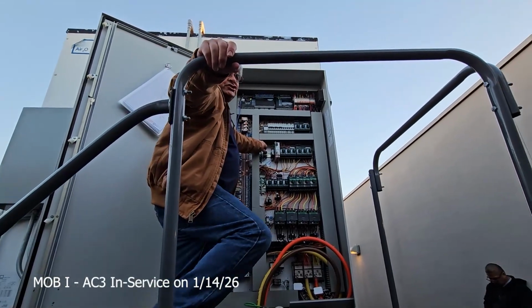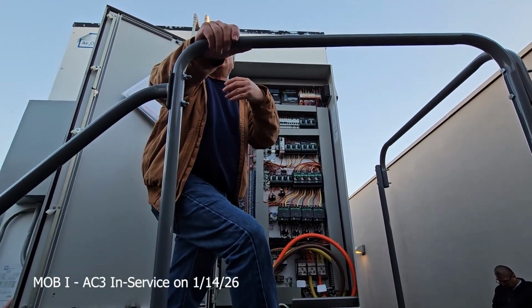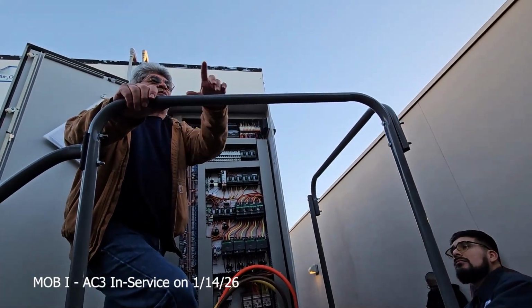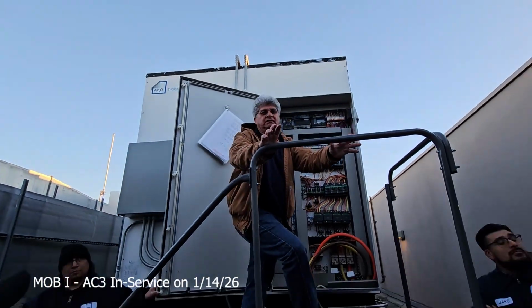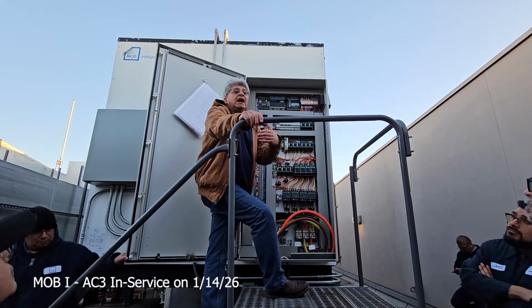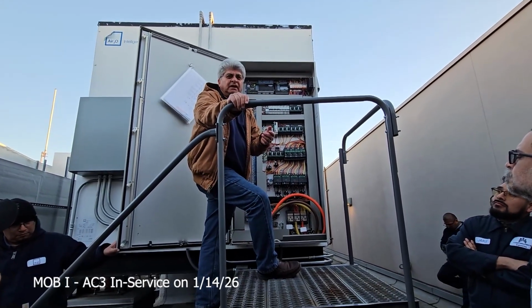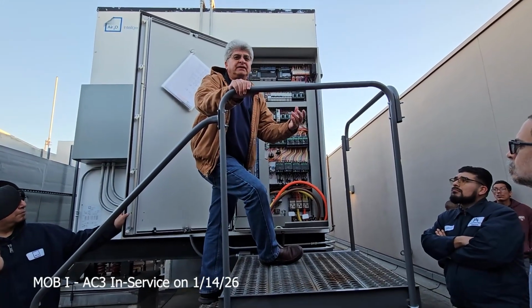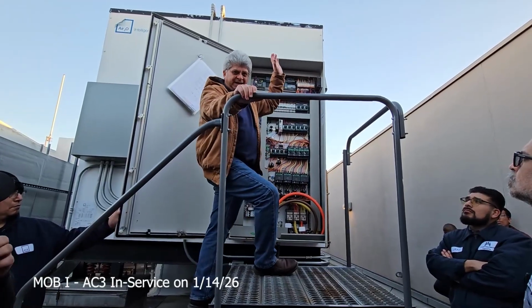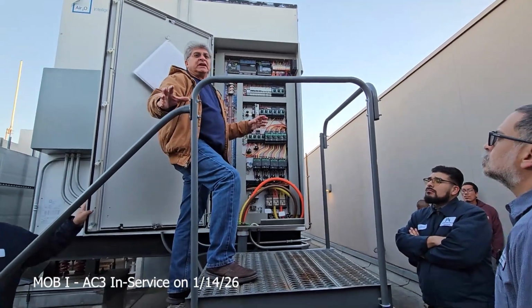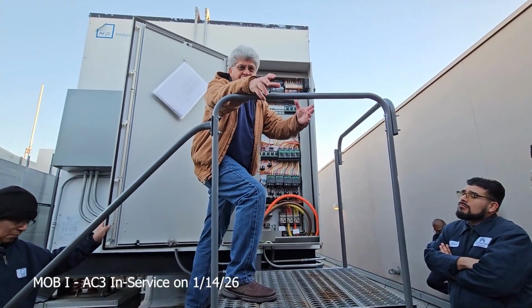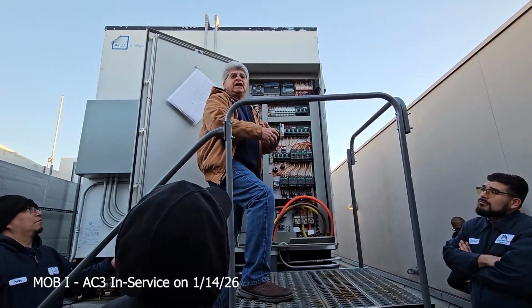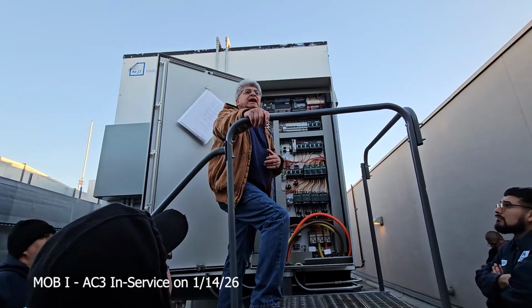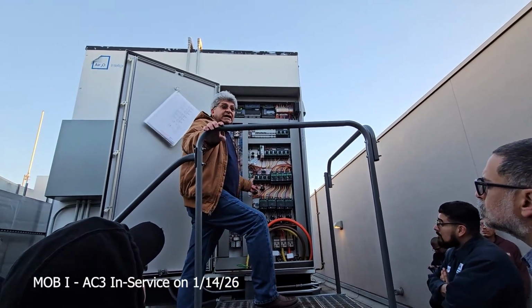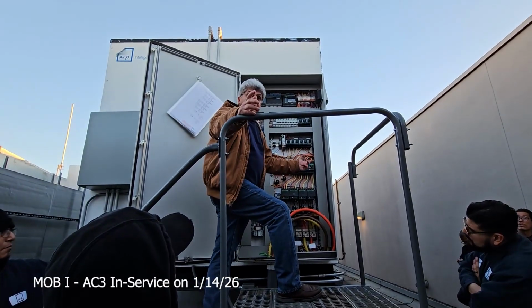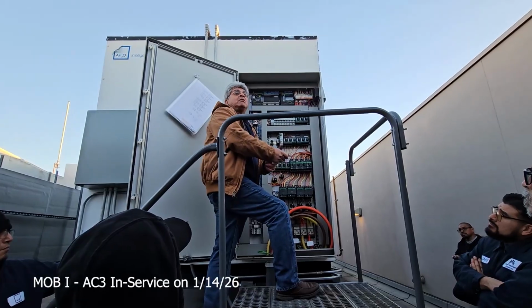To replace that, do we have to shut off the whole unit to replace that fan? My service guys would not. Your boss dictates your safety, how he wants you to work. Right? When I change an outlet in my house, I don't shut off a breaker. I've changed 460 volt breakers live because I had to for the data center. But that's me. That's a couple of my guys that have experience. But I can't tell you how to run it, how to do it at your end. Your shop foreman, your boss may dictate, hey, no, you're not gonna work on anything after hours, shut the machine down, you wanna be safe. Now, if you're gonna work inside here, and you're gonna have 460, you gotta remember that no long screwdrivers, you touch something, so they may not want that.